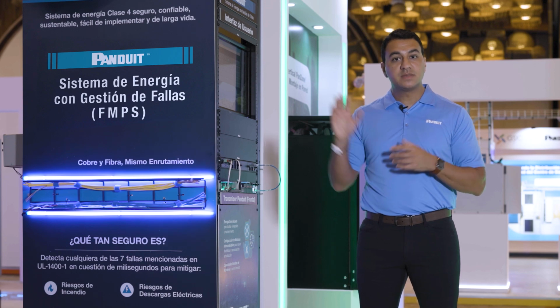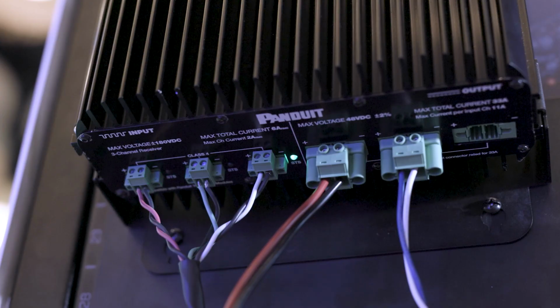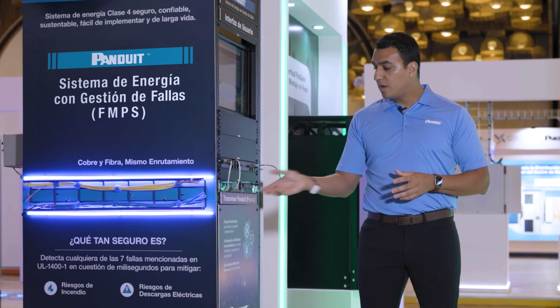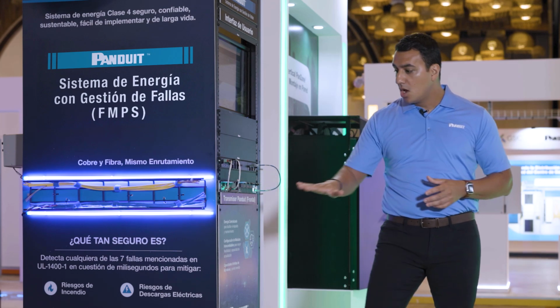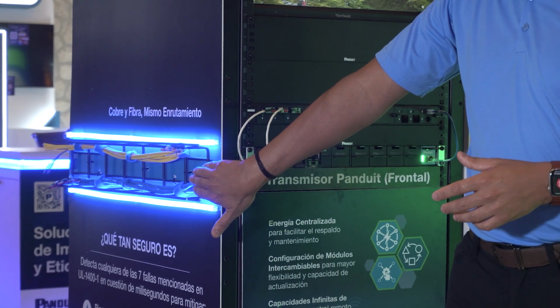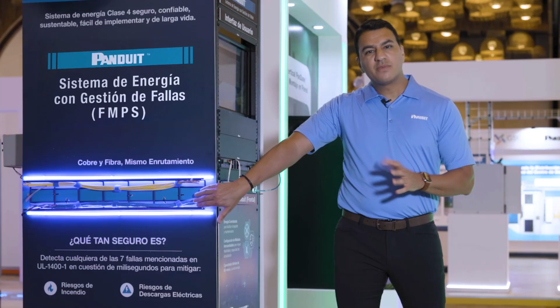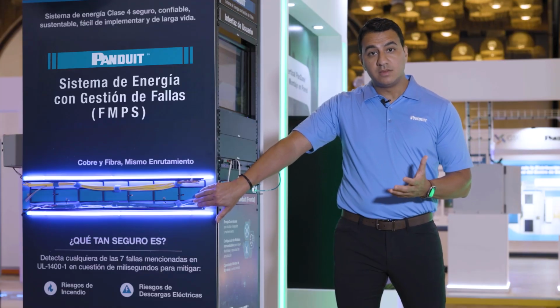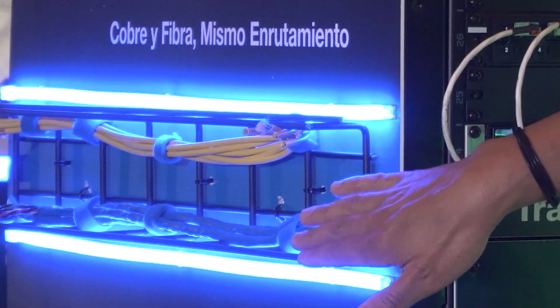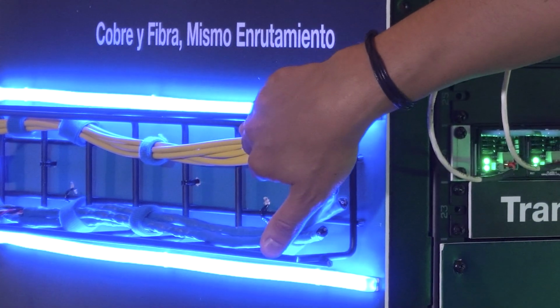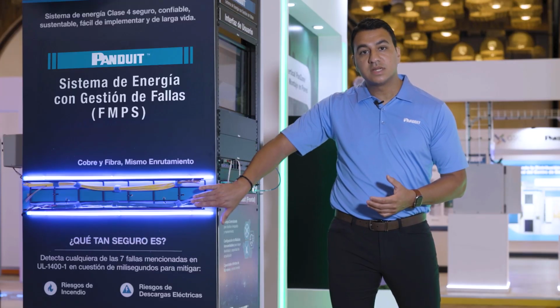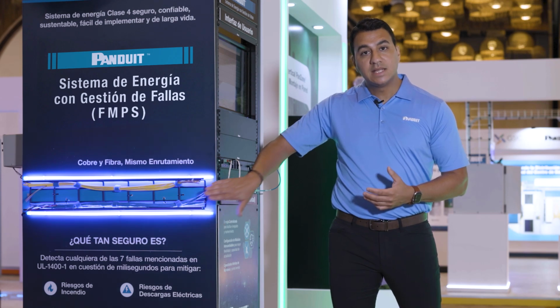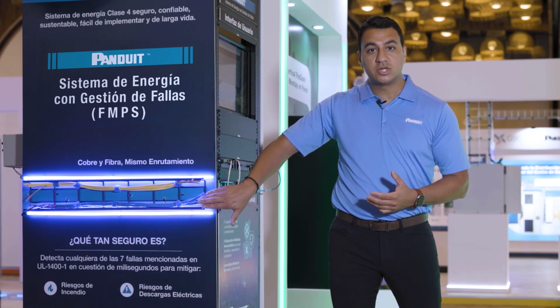The last piece of the system is the receiver on the other side, which I'll show you in a second. So we push class 4 power out from here over cable that looks very much like this. Class 4 cable, anywhere from 16 to 18 gauge, is your typical. And you can see now that you're running copper in the same pathway as your fiber. You don't need to be running this in conduit at all, because again, it's now considered a low voltage installation.